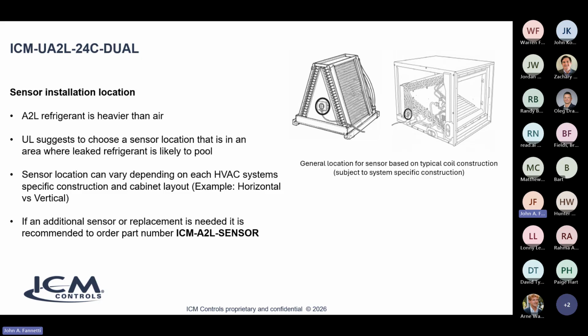So sensor installation. In most of your typical applications, your A2L refrigerant is heavier than air. When we looked at some of the UL guidelines for sensor installation, they're basically saying, find a location where the refrigerant is going to settle, in a low-lying area where the refrigerant is likely to pool. And it can vary depending on each HVAC system's specific construction and cabinet layout. Additional sensors are going to be a replaceable item, and they are part number ICM-A2L-sensor, and we are working feverishly on getting those available to everybody soon. So again, location of the sensor depends on the specific geometrics of the particular unit and the airflow in the unit, but generally in an area where refrigerant is going to collect.